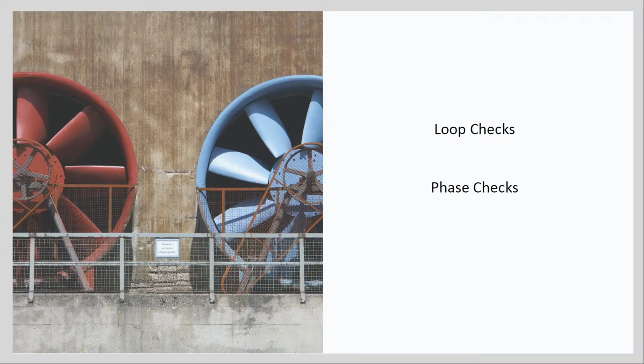So during these hot loop checks, alarm points are verified by stimulating the field device and confirming that the correct alarms are generated and logged. So without the actual plant process started up and running, let's use the example of a level sensor in a tank. There's no liquid or water inside that tank. So during some of these hot loop checks, you may have to stimulate the level sensor to simulate varying levels within the tank.